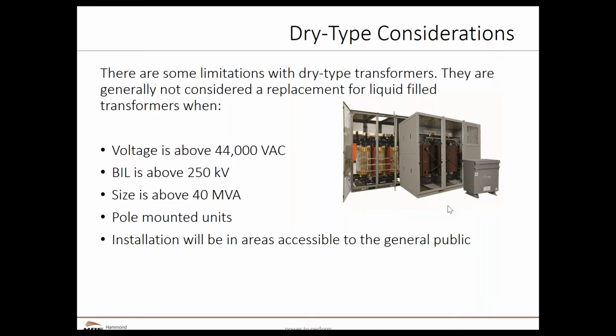And if there are areas that are accessible to the general public, liquid filled transformers often have some advantages. As an example, behind our house in our subdivision here, we have a little green transformer case. It's liquid filled. It's about the size of half of an oven. It's only about 2.5 feet tall. Kids go climbing on it. That is a hermetically sealed unit. And I don't like the kids climbing on it. In fact, I take them off. They shouldn't be. But a completely ventilated unit probably is not a good idea to install in an application like that, again, because it has a lot of accessibility to the general public.